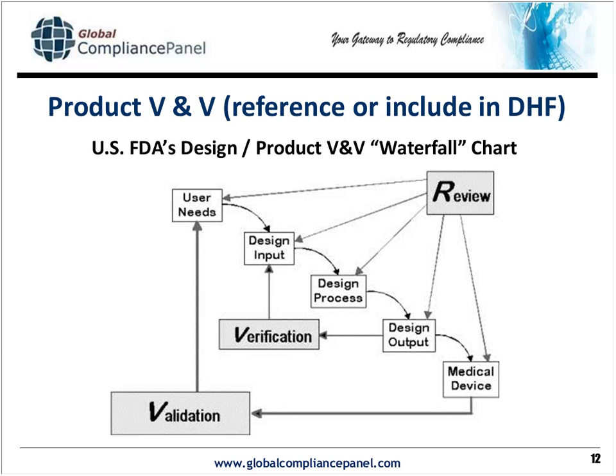And then the ultimate result is compiling all these verification documents, etc., into a package that becomes part of the validation that your anticipated product has been met by the resulting product, as spelled out in user needs and the resulting physical product, both the test data on the physical product and the review of the documentation that defines that product, the device master record, if you will. This becomes the product validation, which is part of the design history file.